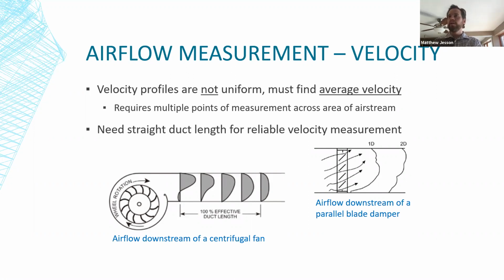You can see on the diagram with the fan, as the air comes out of that fan, all the velocity is pushed up toward the top of the duct, which makes sense. That's the direction the fan is rotating. And it's just pushing all the air up there. Down toward the bottom of the duct, the air becomes stagnant or even moving backward. There's an eddy there. So if you were to try to take a duct traverse right here, it's going to be all over the map and very inaccurate. Your airflow is turbulent.